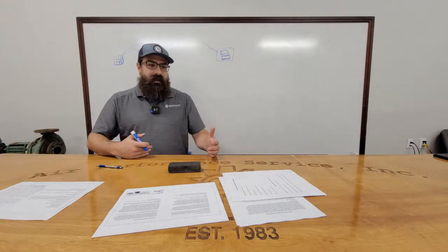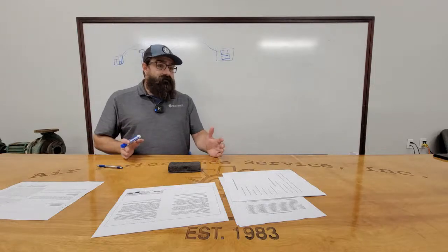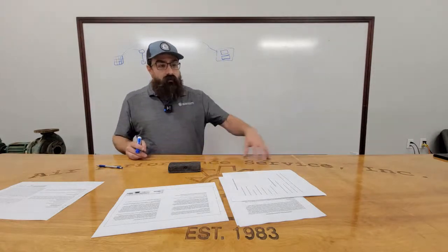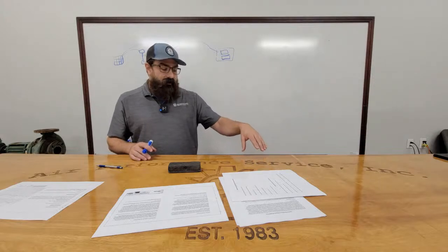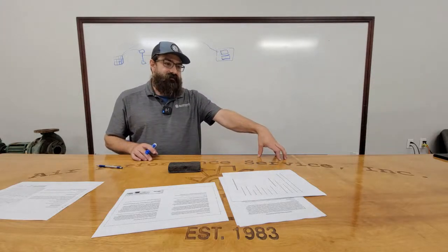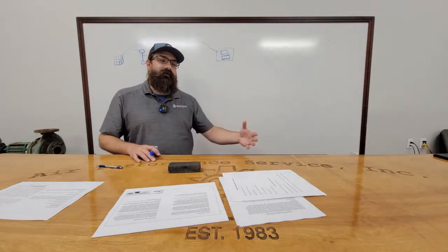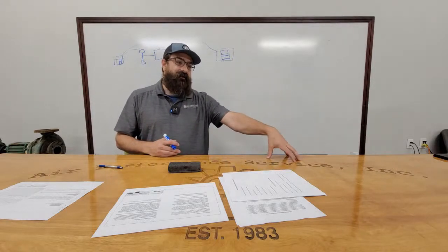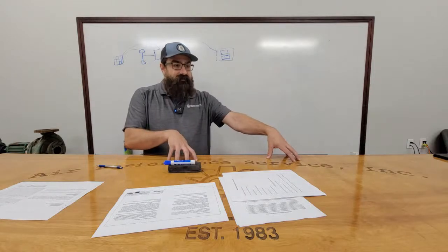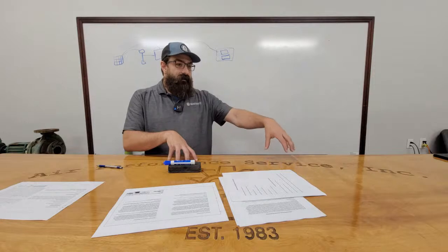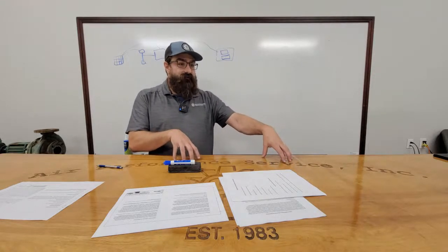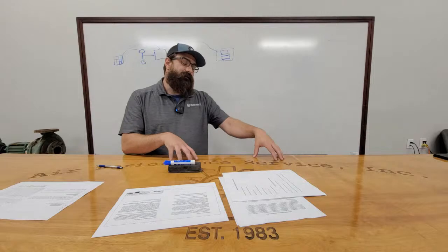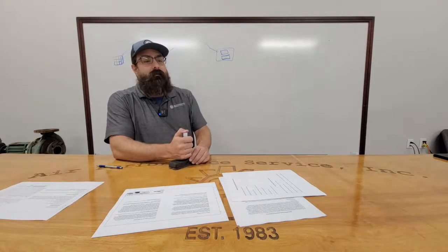Okay. We use load, not averages. Averages work just fine. You just have to pay more attention to what you're setting the building as. If you're using a global set point for the entire building, they work perfectly fine. If you've got one customer who says we can't have it any higher than 80 degrees in our space, and another customer that says 90 is fine, then you wouldn't want to do temperature-based averages. You'd want to do load-based averages. So you can have this whole side set for 85 for load, this whole side set for 80 for load. They're not going to call at the same time because their set points are different, but based on load, this side's going to load up faster than this side would. So it's our preferred way, and it's how most stuff is done.